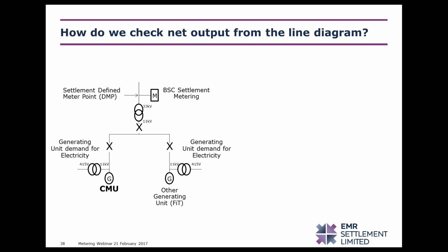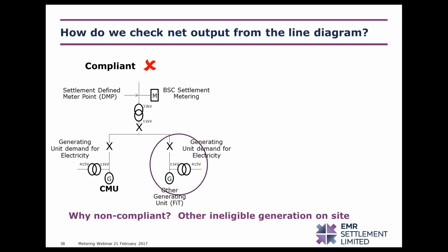So how do we check the net output from the line diagram? On the left, we have a diagram of a site which has 2 generating units and BSC settlement metering at the boundary point. One of the generators forms a CMU, whereas the other does not. The meter at the boundary point records all the electricity associated with both generating units. For this reason, this CMU is non-compliant, and that's because there is other ineligible generation on site which is being accounted for in the metered volumes at the boundary point meter.